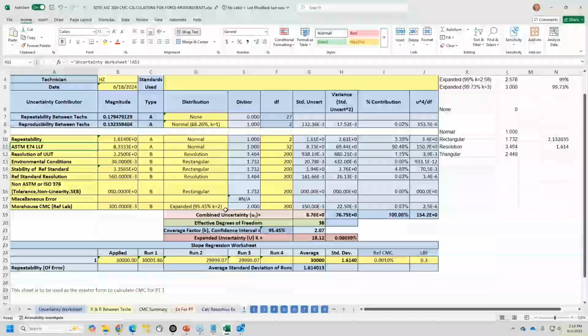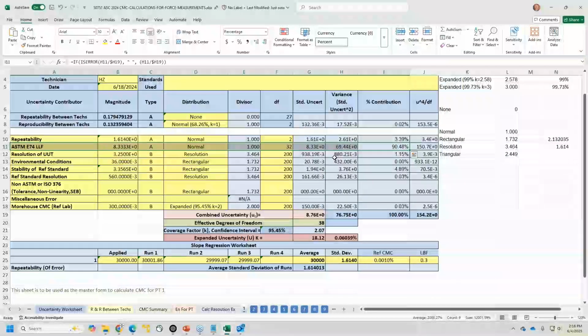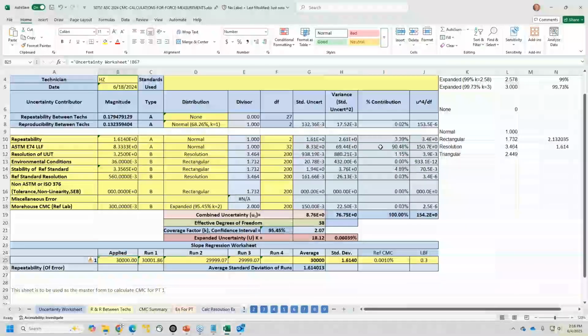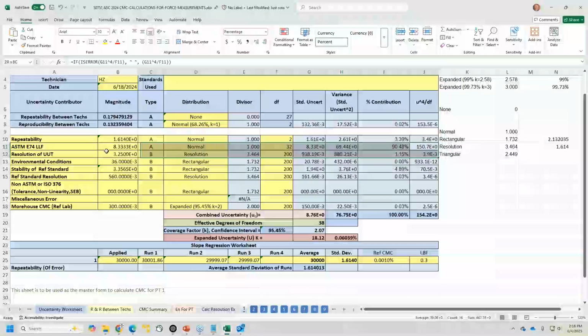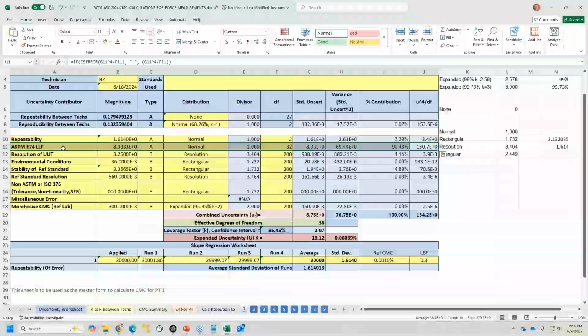But what this does when it's all said and done is I can click each individual point using the Welch-Satterthwaite, which the GUM recommends. And I can look in and start making assumptions or decisions based on things. At that 30,000 pound test point right here, the percentage of contribution from that ASTM lower limit factor is dominant. 90.48% of my overall budget.